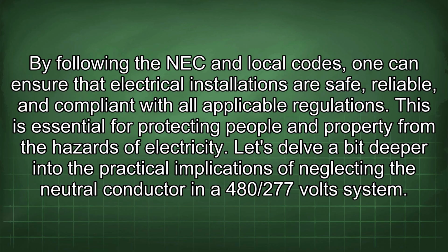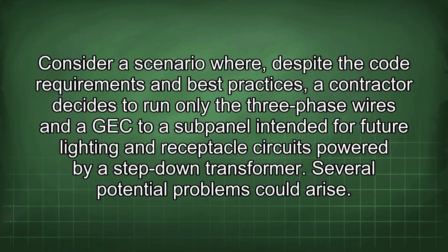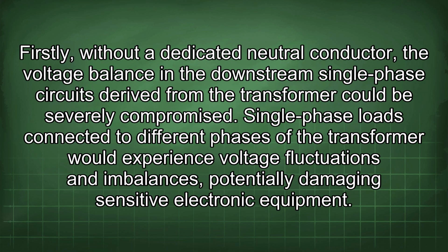Let's delve a bit deeper into the practical implications of neglecting the neutral conductor in a 480/277 volt system. Consider a scenario where, despite the code requirements and best practices, a contractor decides to run only the 3-phase wires and the GEC to a sub-panel intended for future lighting and receptacle circuits powered by a step-down transformer. Several potential problems could arise. Firstly, without a dedicated neutral conductor, the voltage balance in the downstream single-phase circuits derived from the transformer could be severely compromised.